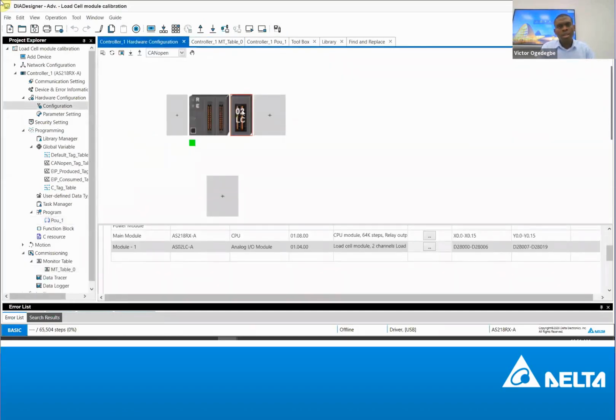So if you double click on this, I'm using DIADesigner. DIADesigner is one of our DIAStudio software. You can use this software, DIADesigner, to program our HMI, our inverter, our PLC, and other devices. It's one software, and this same software you also use to configure the load cell module.